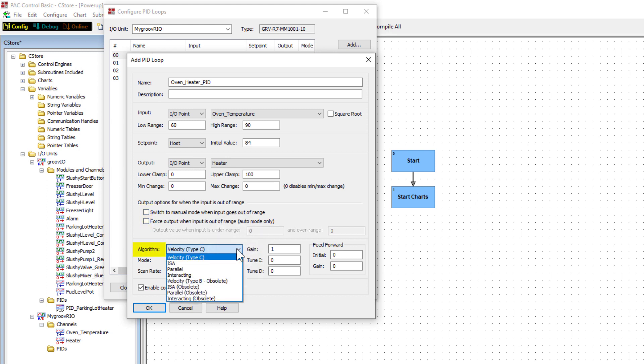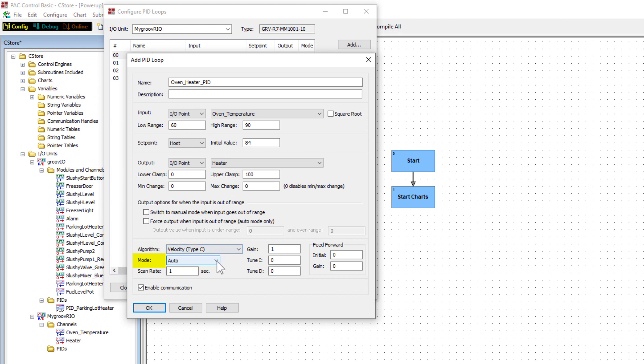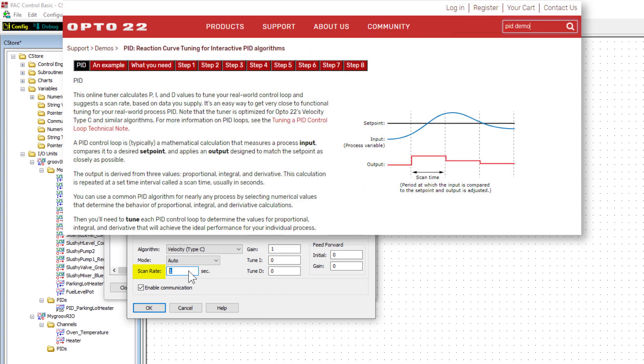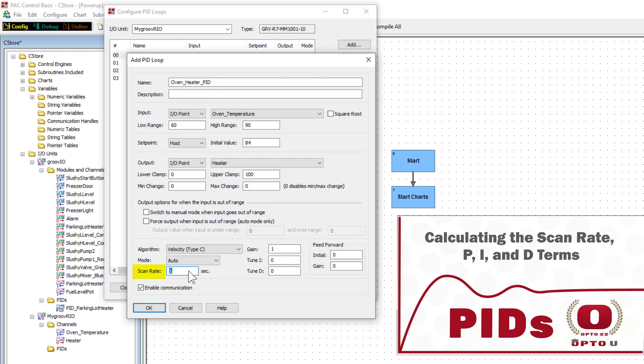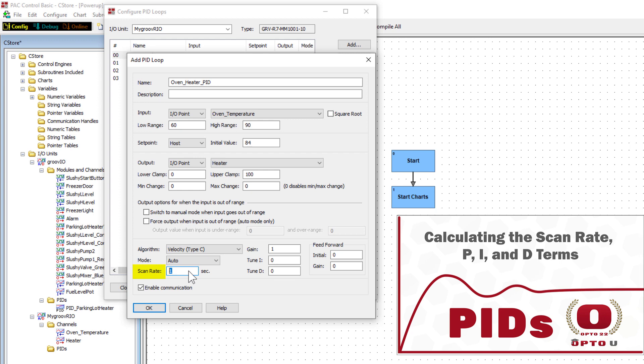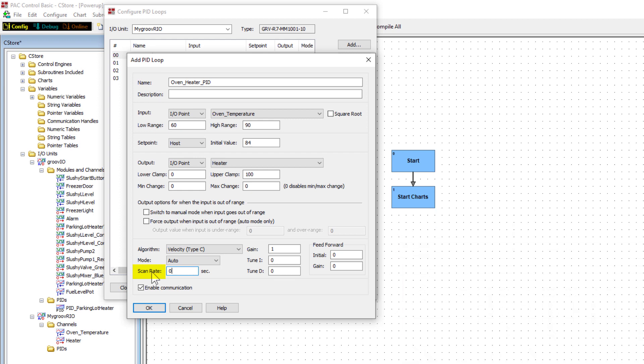Velocity type C is the default PID algorithm. No one algorithm is right or wrong. It's what you choose to work with. Be sure auto is selected so that the PID is activated when the strategy starts. Manual mode is used for debugging and lets you control the PID. The scan rate is set to a default value of 1 second but you need to modify this value for your PID. To properly find this important PID value, use the PID tuning demo on the Opto22 website. We're going to go into more details in a future lesson, calculating the scan rate P, I, and D terms. For now, enter a value of 0.014.